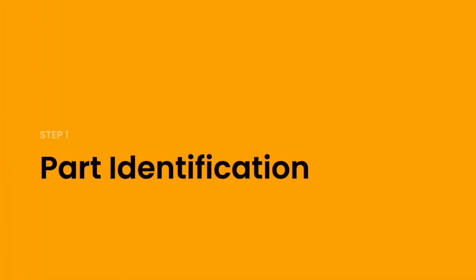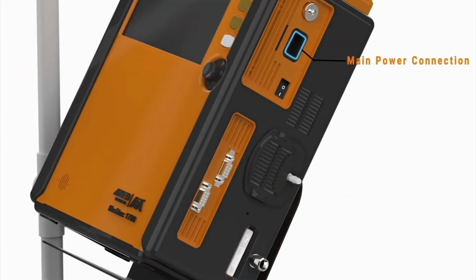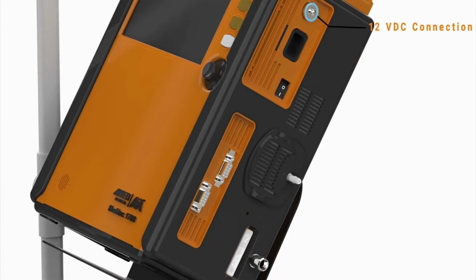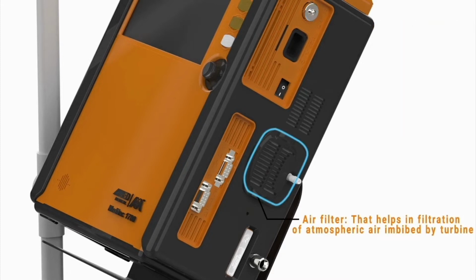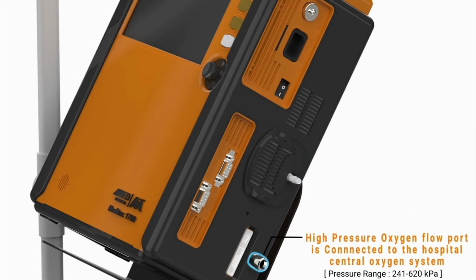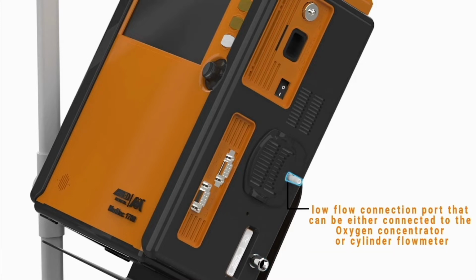Let us first learn the different parts associated with this ventilator. On the right side of the ventilator, we have the main power connection. A 12 volts DC port that could be connected to the ambulance power source. The air filter present below that helps in filtration, and it needs to be cleaned every 5 days. The high-pressure oxygen flow port is connected to the hospital central oxygen system, and if you are transporting the patient via ambulance, then you could connect the low-pressure oxygen flow port to the oxygen concentrator.